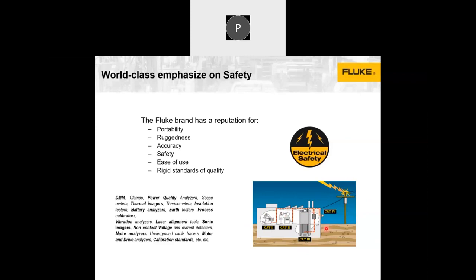Interestingly, you are also working at various voltage levels, and this is where you have to choose your measuring devices appropriately. If you choose a category 1 rated DMM, oscilloscope, or other test instrument and use it in a higher category environment, you will be at risk of electrical shock or electrical hazards. That's why this is very important, and that's why we stress upon this particular safety reason.